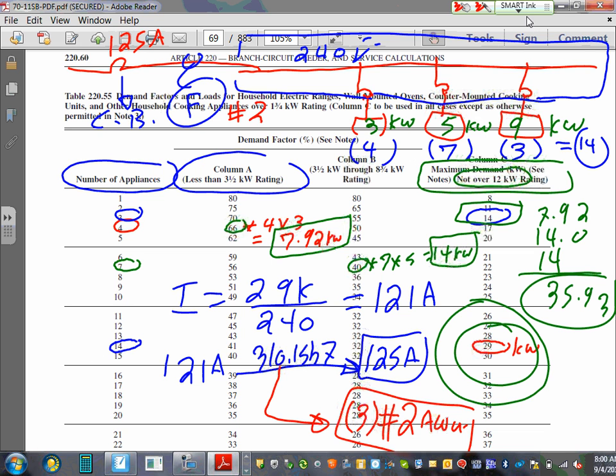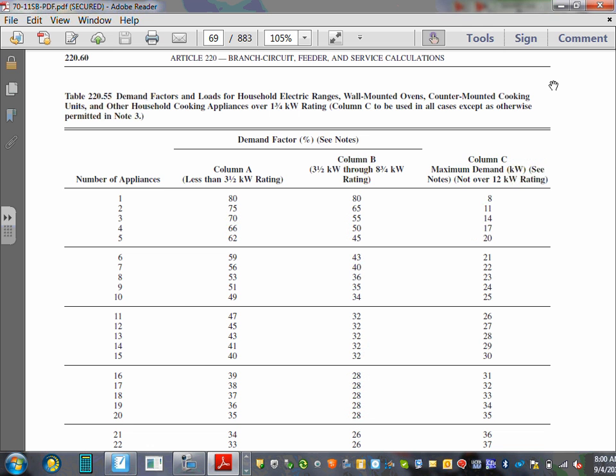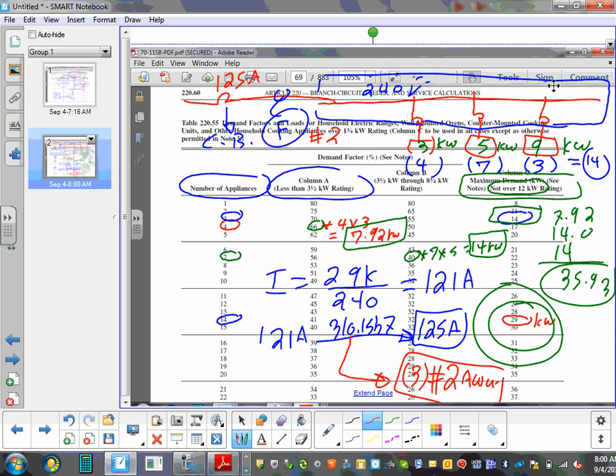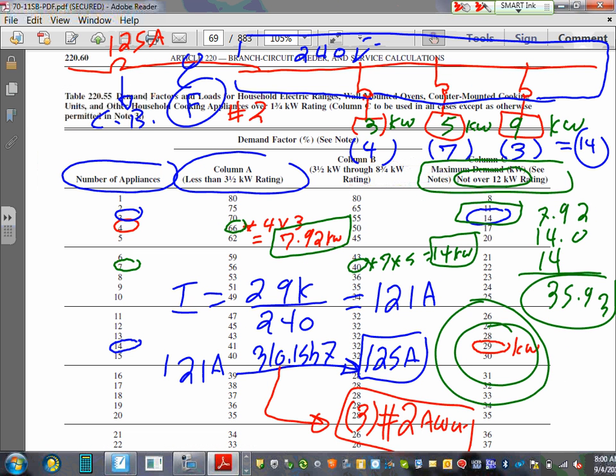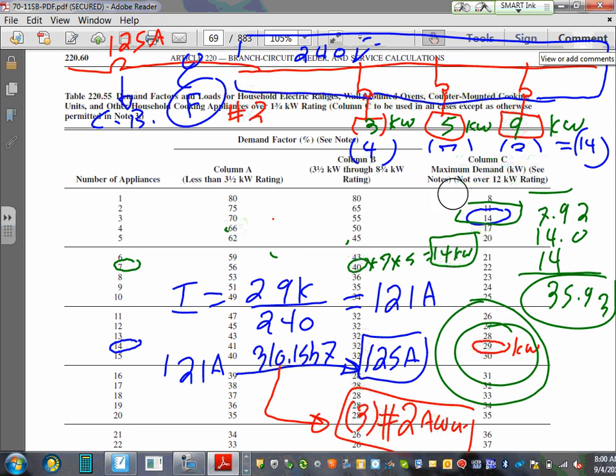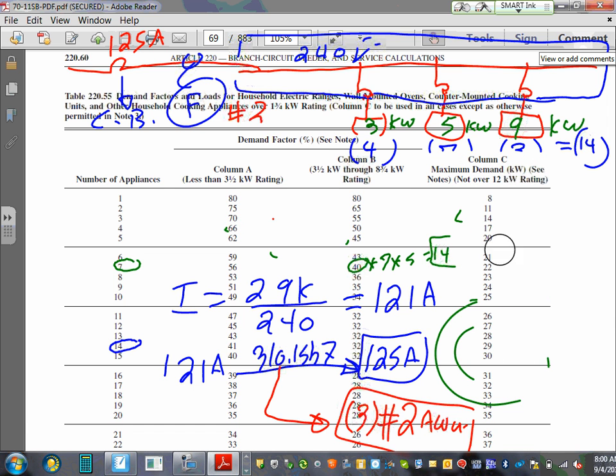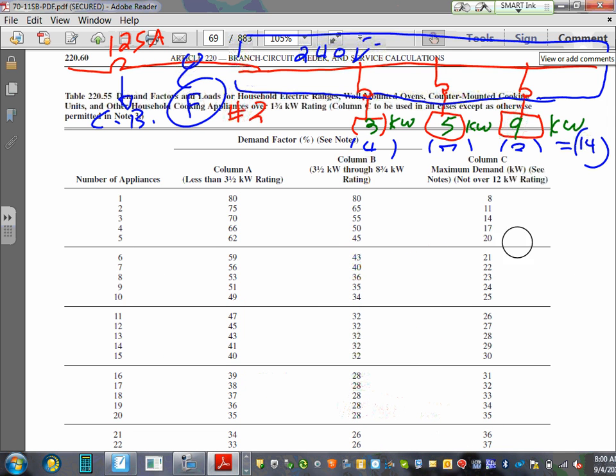So let me take a snapshot of this. So that's what we now I'm gonna erase this, guys. So we size the system. Okay. All right. So I size the system. I'm going to put the sizes here. Circuit breaker is already sized. So these are 3 conductors, number 2, right? That's what I came up with. Okay, so I have a 125 amp service, 3 conductors, number 2, feeding all these.